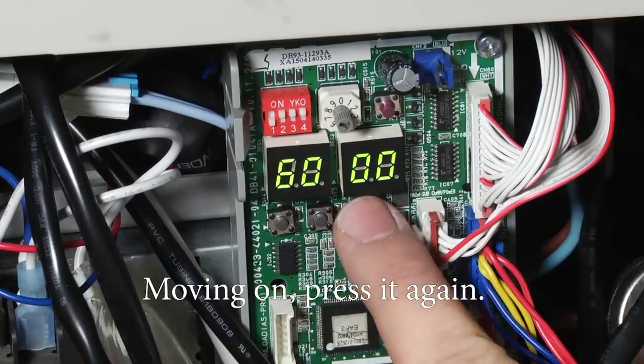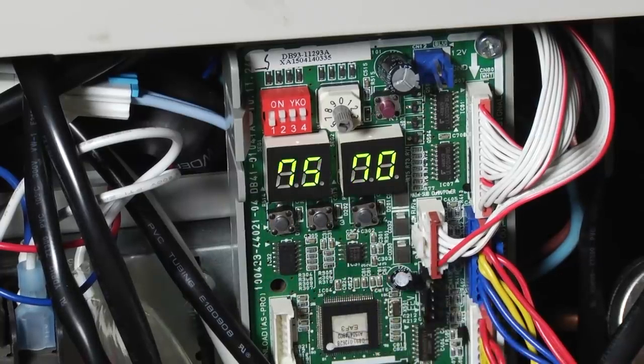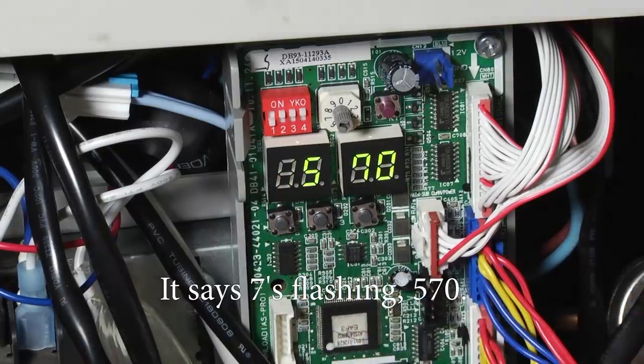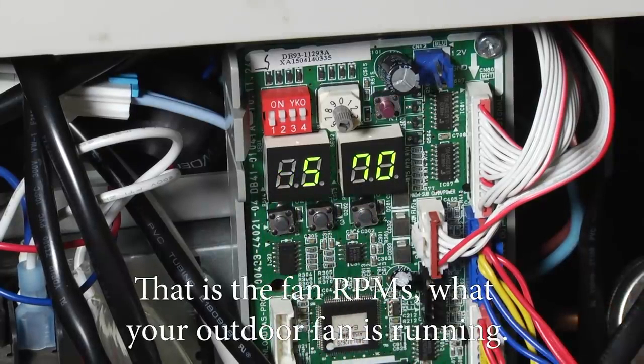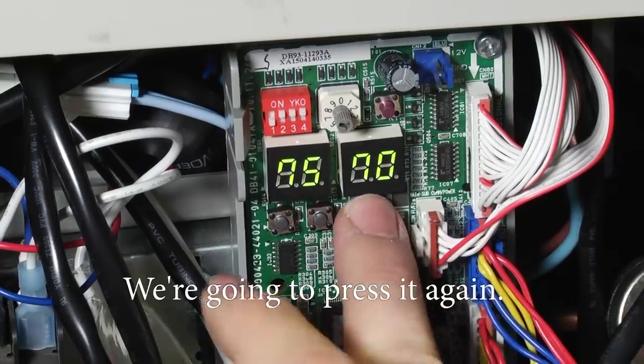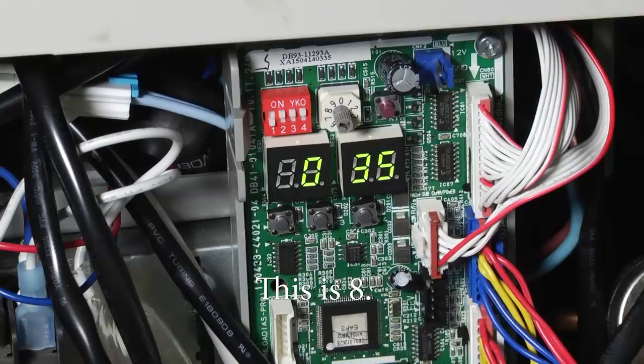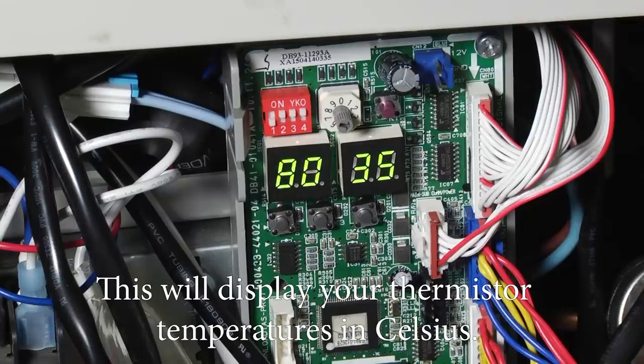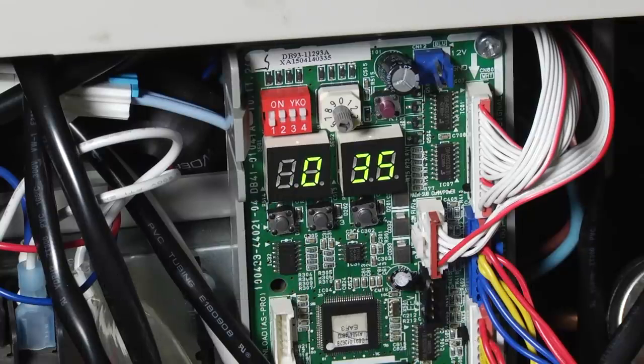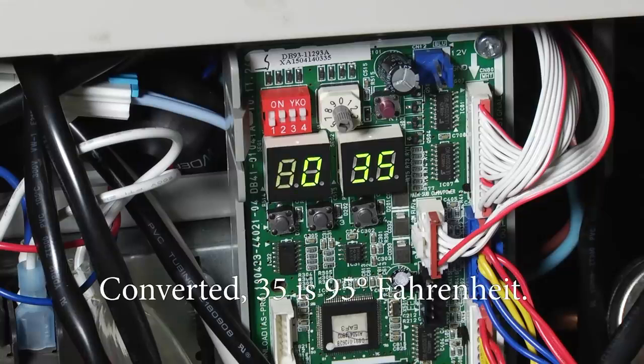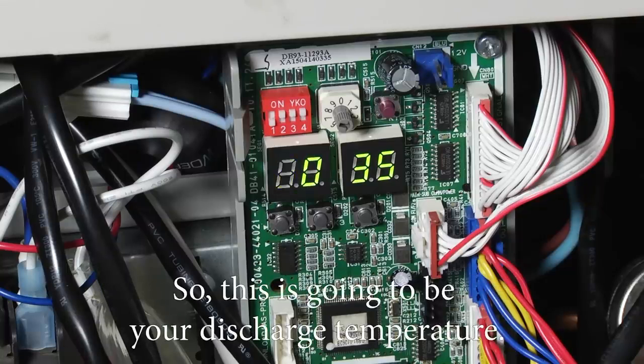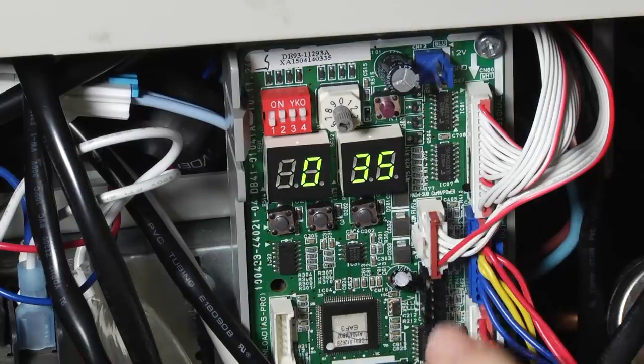All right, moving on, press it again. It says 7 is flashing, 570, that is the fan RPMs of what your outdoor fan is running. We're going to press it again, and this is 8. 35 is in Celsius. This will display your thermistor temperatures in Celsius. Converted, 35 is 95 degrees Fahrenheit. So this is going to be your discharge temperature.